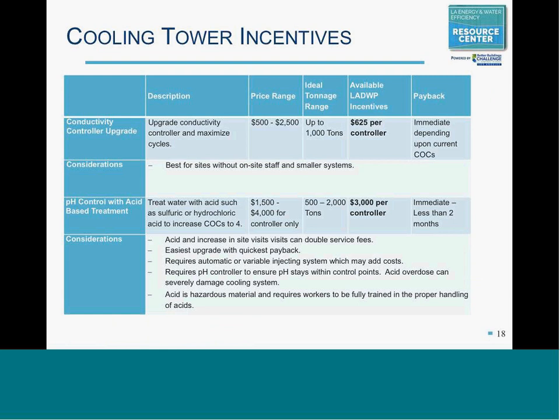For cooling towers, there are four major types of upgrades for water treatment. First is increasing your cycles of concentration with standard chemical treatment and better monitoring. This works well for most towers when water quality is better and there may not be on-site maintenance staff. LADWP offers $625 for installation of a conductivity controller, which should cover the cost, and payback should be immediate. The primer walks you through this in more detail.